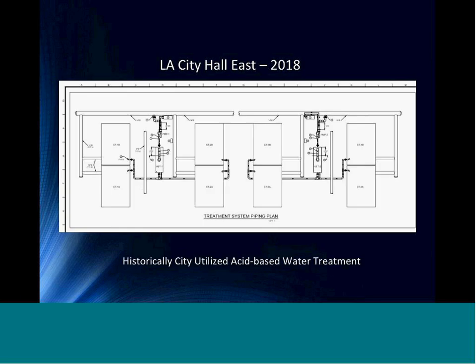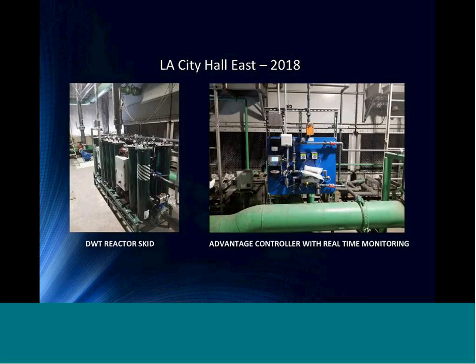Next slide, please. This is just a general layout of the process. We installed 2 skid reactors. These are side stream reactors using an electrochemical process. What we're able to do is take the makeup water coming into the process, pull it into our reactors, pull out unstable mineralization, as well as sanitize the process water, generate chlorine and hypochlorous acid from the chlorides in the water, and go back into the basin. Next slide, please.